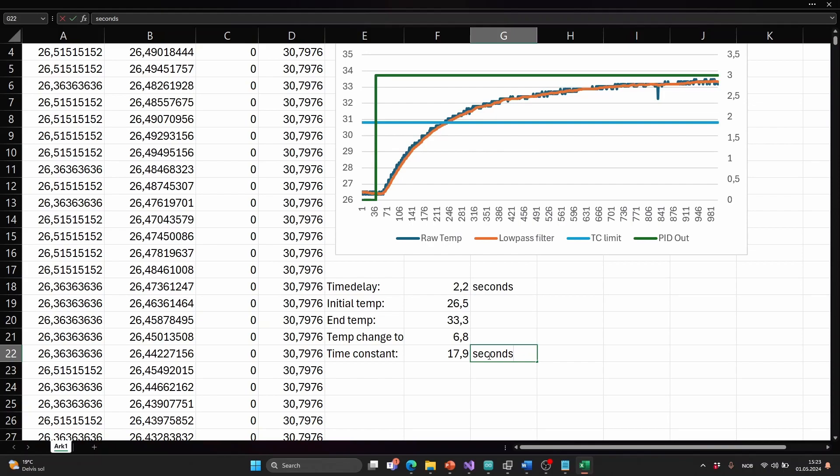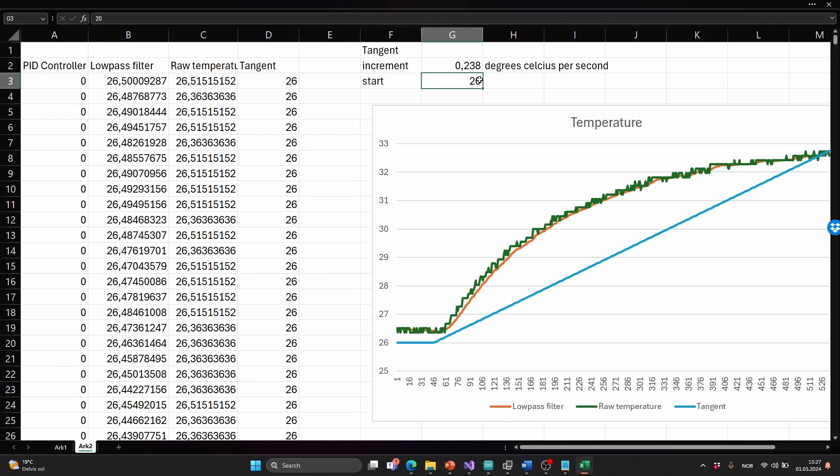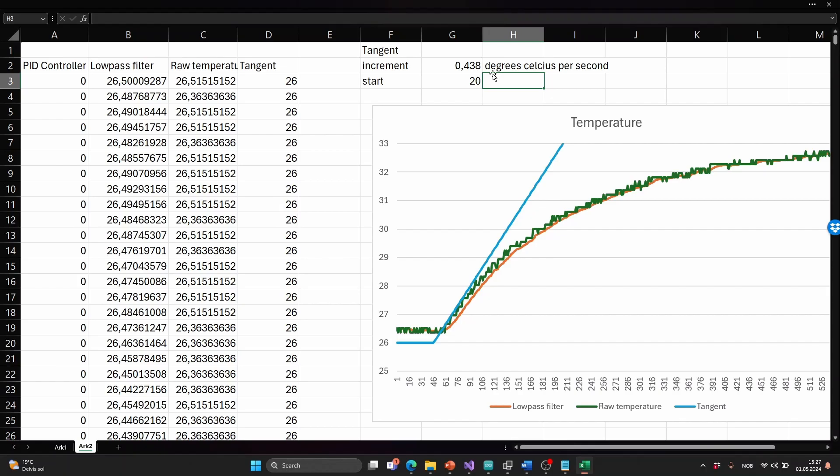The next thing we need is to find the steepest tangent along this curve. So I will try to fit this blue line tangential to this temperature curve. I do that by changing this value. And I just test the different values until I think it's around the tangential. I think that's good. 0.438 degrees per second. That's the fastest change.